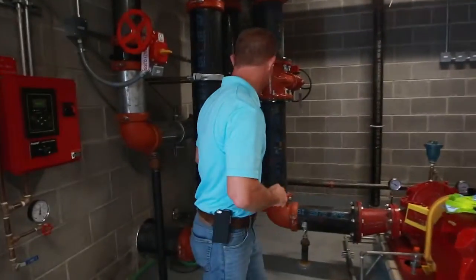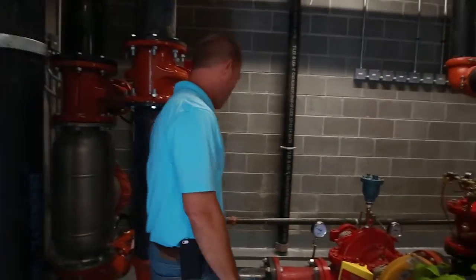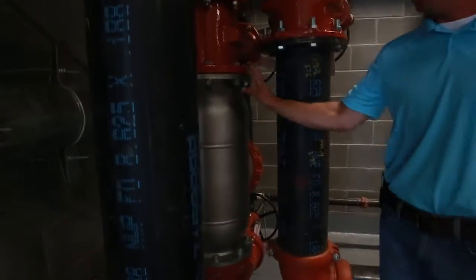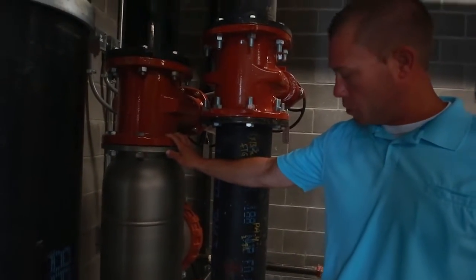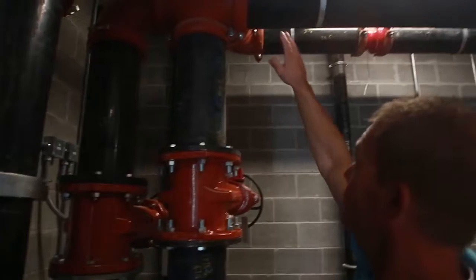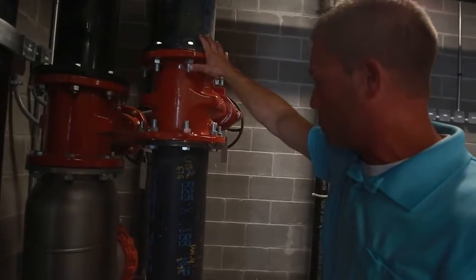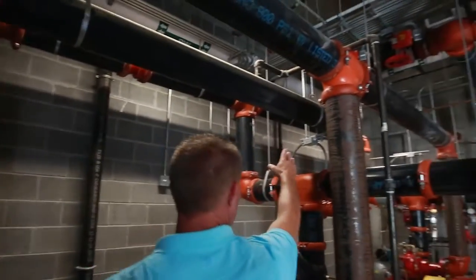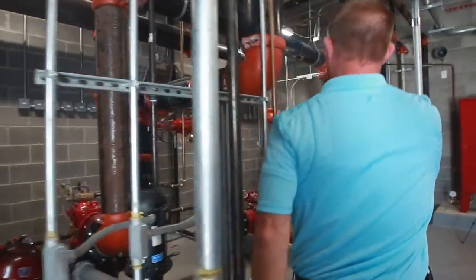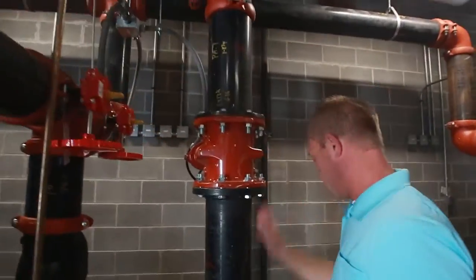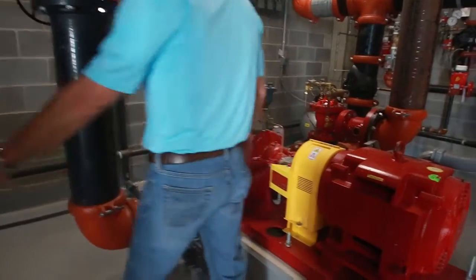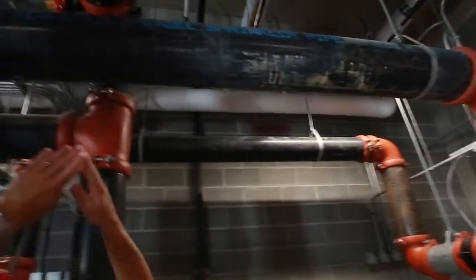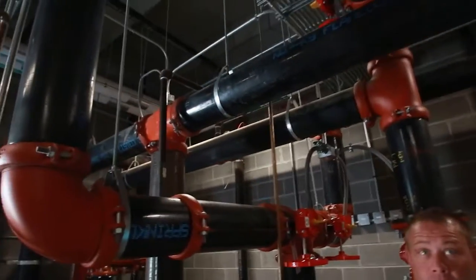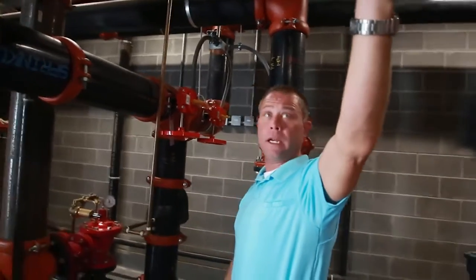Here at the CUP, we have 2 fire pumps. We have one feed. It's going to come into the backflow preventer, double check, and it's going to go on over here, come down. This is to the suction side of pump 1, and it'll continue. Follow me over there to that T, and it'll go to your backup fire pump, into the suction side here. You have your discharge for the pump, which will come around and connect here to one feed that goes and feeds building 5, 6, the parking garage, and the tower.